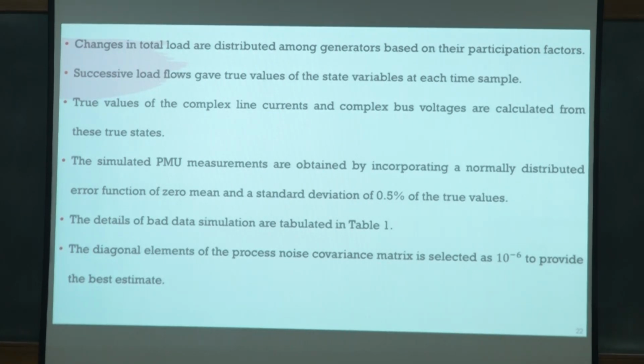Now, if the load, say for example, comes down to 50 megawatt, how will these generators share? They will share in the same proportion, the way they were doing for 100 megawatt load. Now they will share 25, 15 and 10. That is participation factor. So, using the generators' participation factors, whatever system loads are changing, that is being shared by the generators.